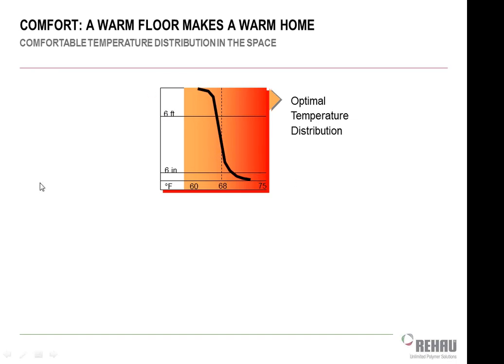So from the floor to basically the ceiling, I need to have the same temperature within 5 degrees, which sounds like a wide range, but if you go home tonight and start taking temperatures at your floor and taking them at your ceiling, you're going to find 12, 15 degree distribution temperatures between those areas. Keeping it within 5 degrees is very difficult to do with an air side system. You can do it with proper diffuser placement and directional diffusers, but it's a lot easier to do it with chilled beams or radiant cooling or radiant heating panels or radiant floors like we're talking about today.